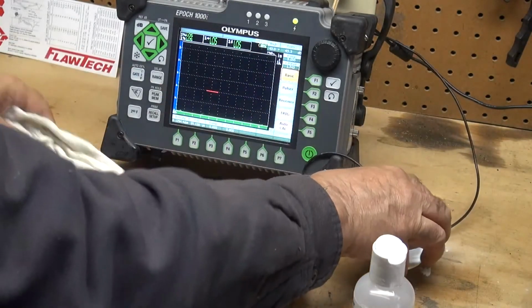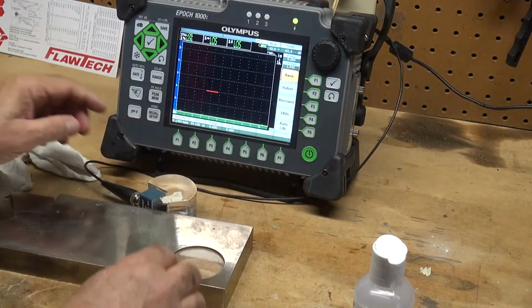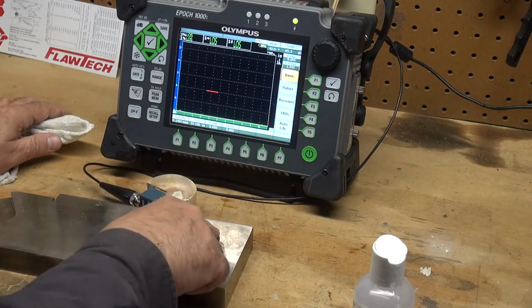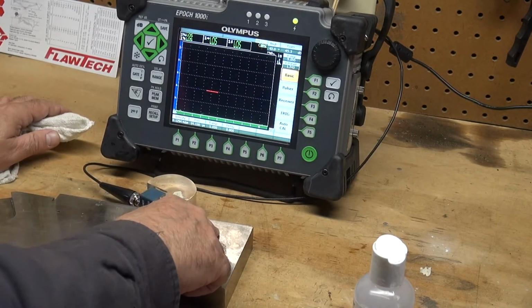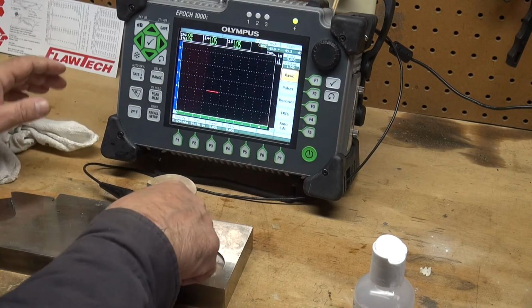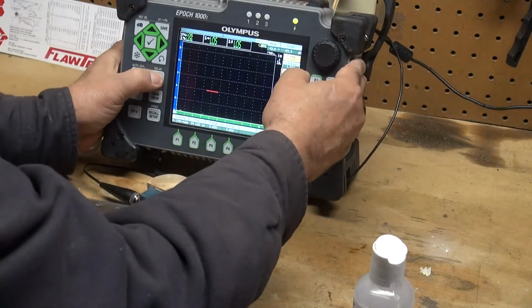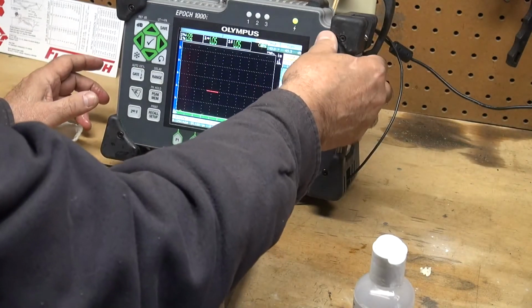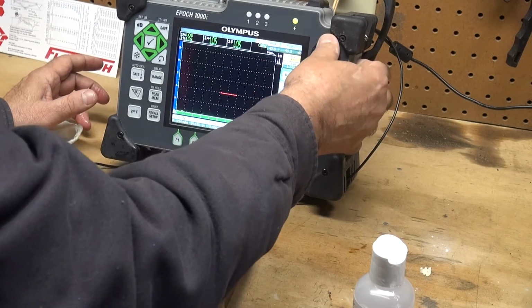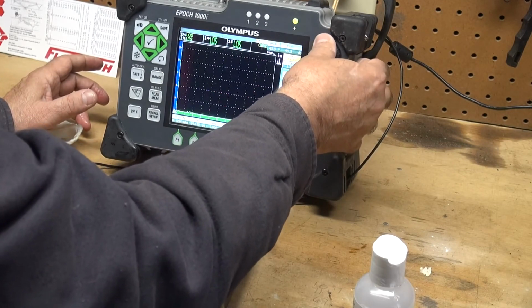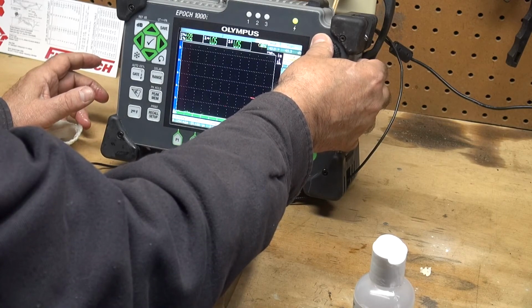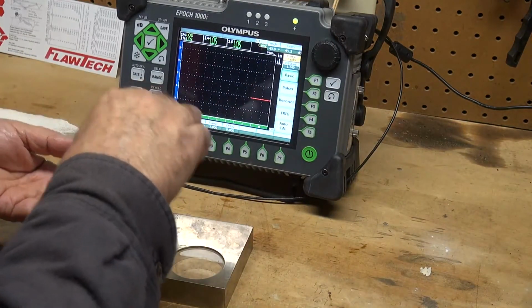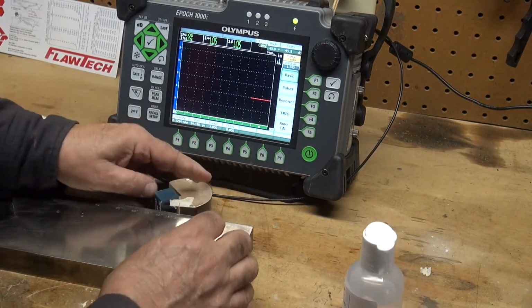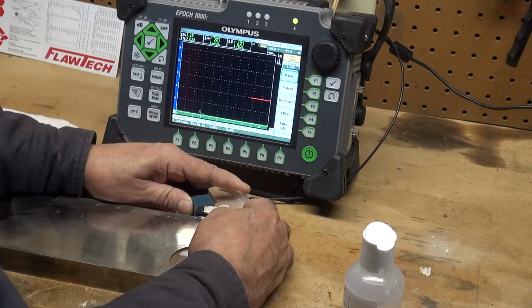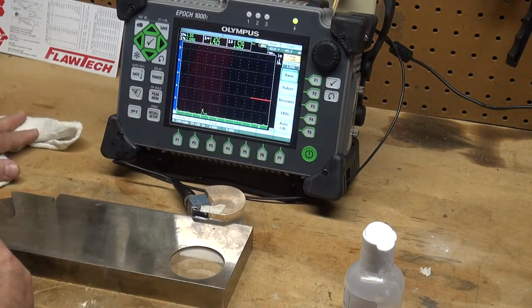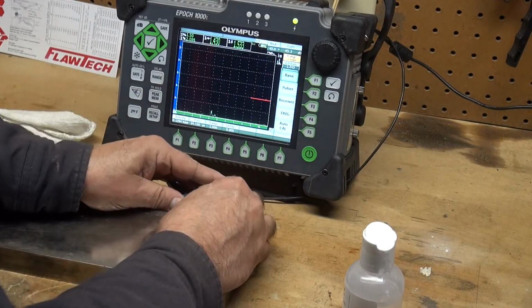The last thing I want to show you is to set your reference sensitivity. The IIW block has a 60 thousandths through hole that is 0.6 inches deep. So I want to change my range. With 45 degrees, I only need about a 2-inch range to find this hole, just to make use of our screen width. Alright, change my range to 2 inches. There it is. I couple this up and I'm going to use my 45 degree to find this side drilled hole. I see it popping up right about here.